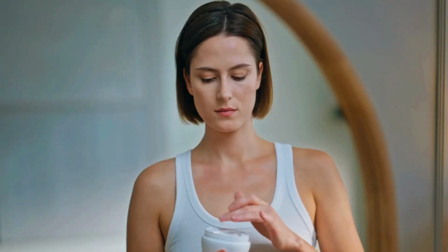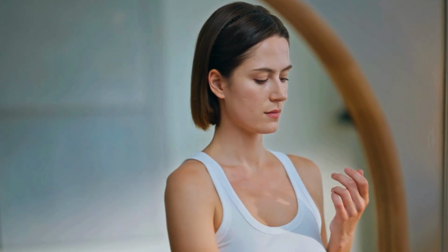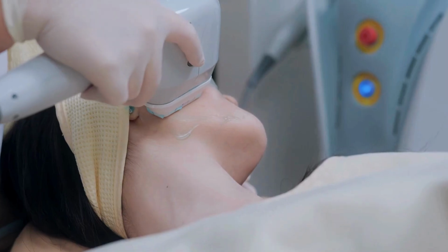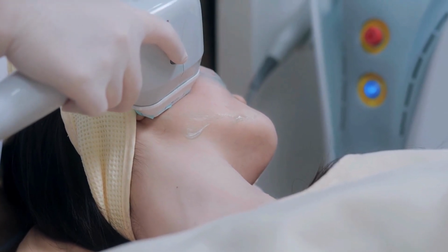Here's the actual mechanism. The HIFU transducer emits ultrasound waves that pass through the epidermis and dermis without causing damage, then converge at specific depths depending on the cartridge used. 1.5 mm: superficial dermis, collagen stimulation. 3.0 mm: deep dermis, superficial fat and fibrous septa. 4.5 mm: SMAS layer, facial structural support. More advanced systems also offer 6 mm and 9 mm cartridges for body applications.